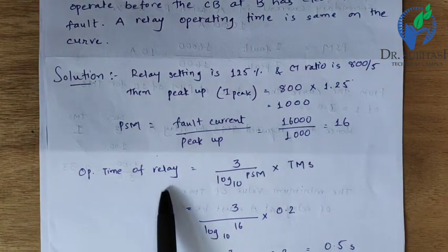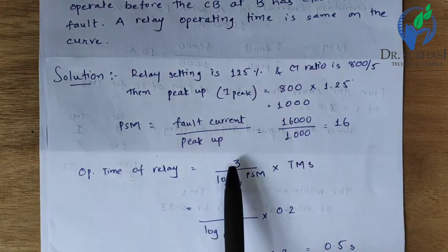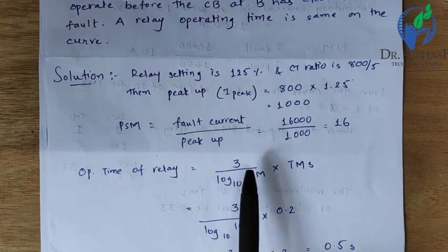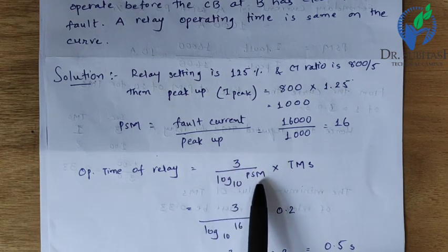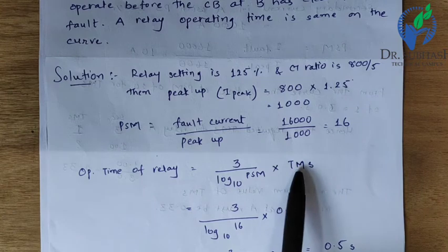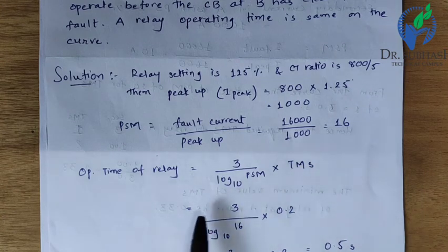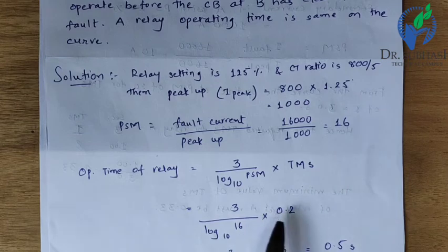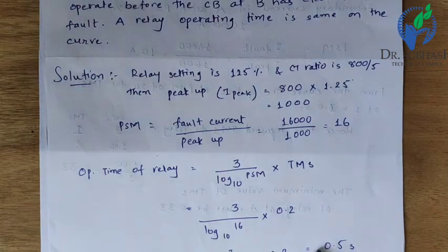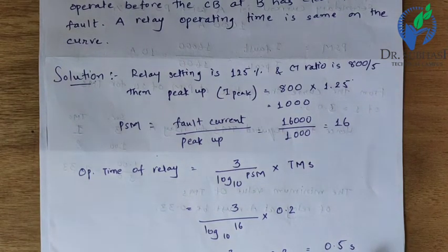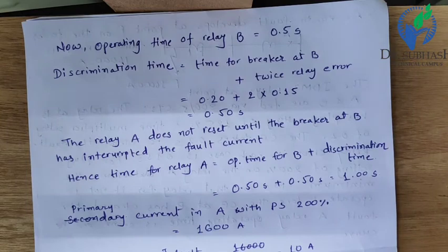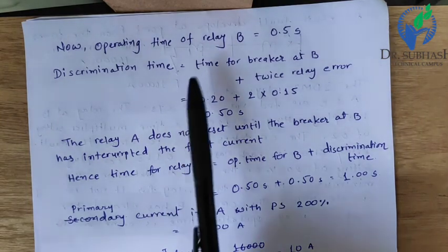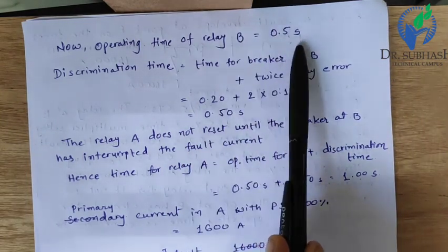Operating time of relay B is calculated using the equation: T = 3 / (log10(PSM)) × TMS. Substituting PSM = 16 and TMS = 0.2 gives an operating time of 0.5 seconds. So relay B operating time is 0.5 seconds.